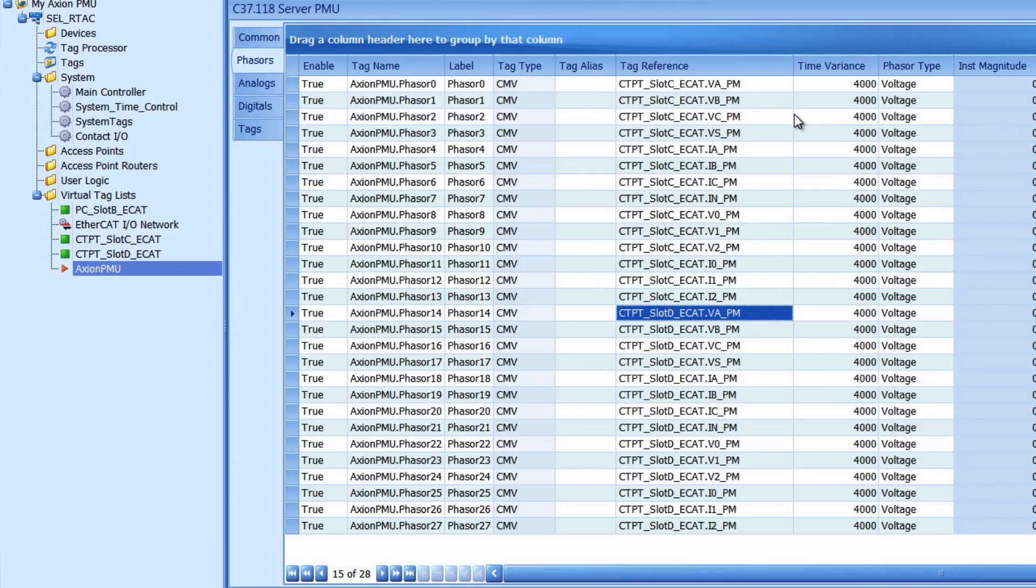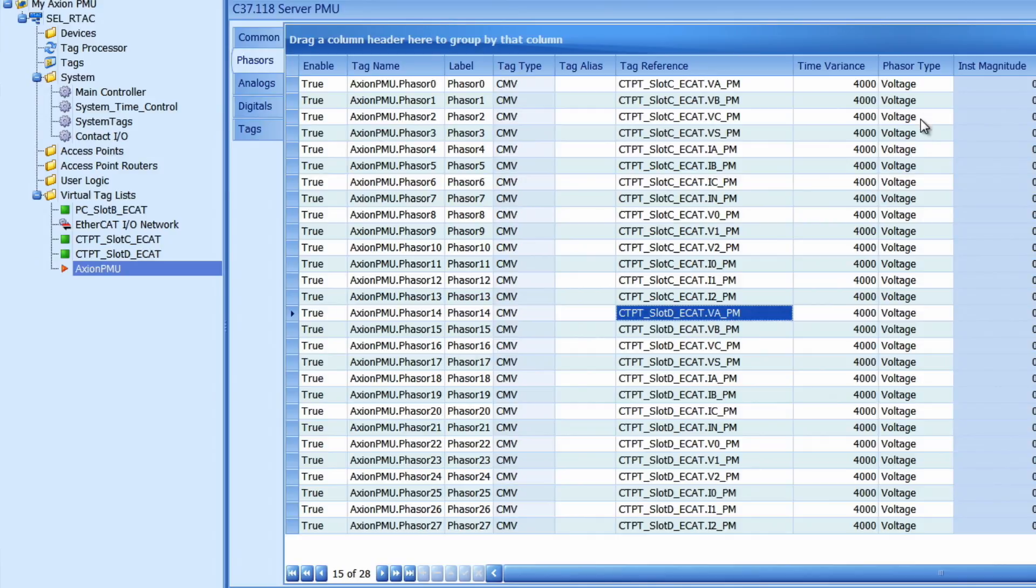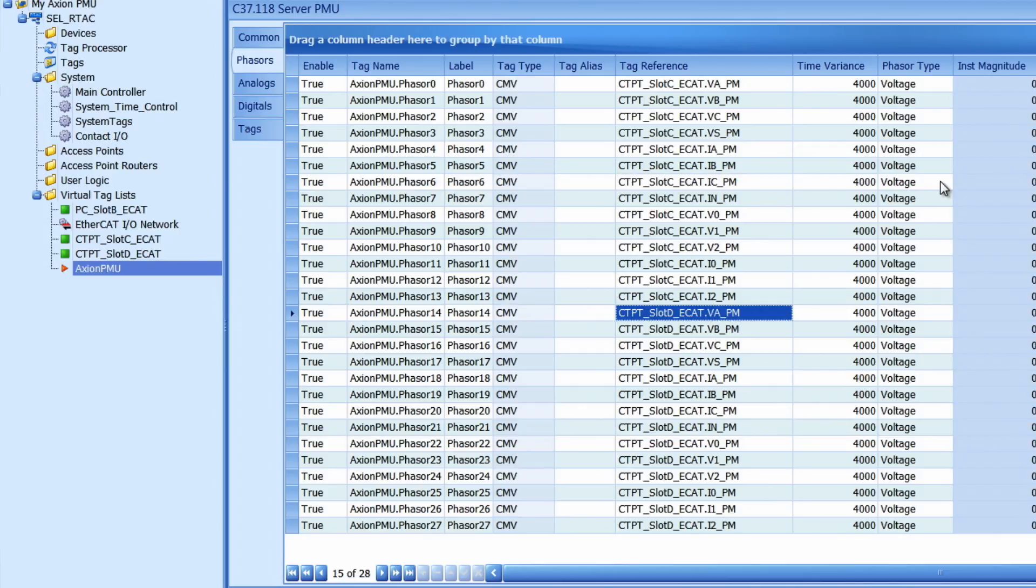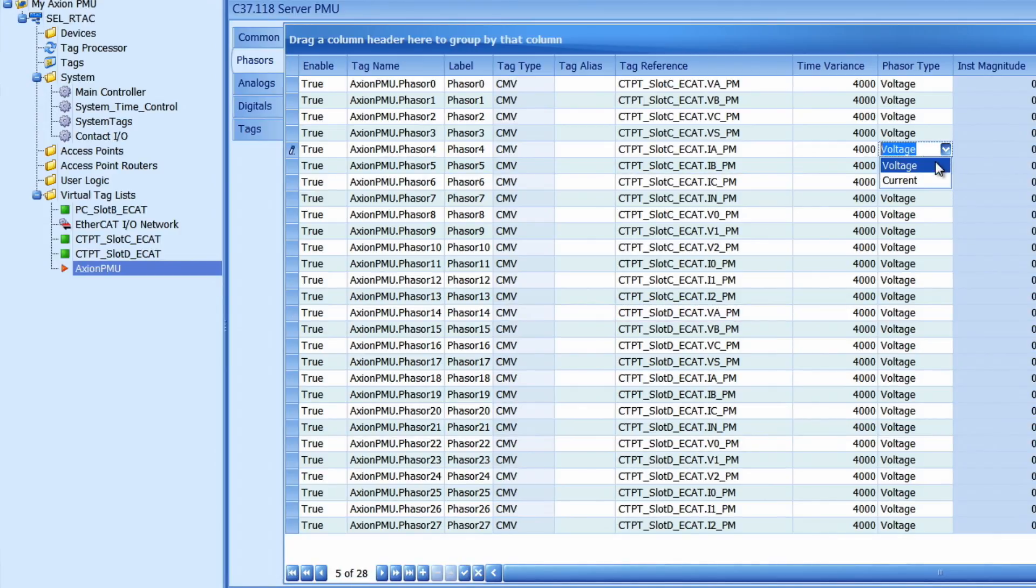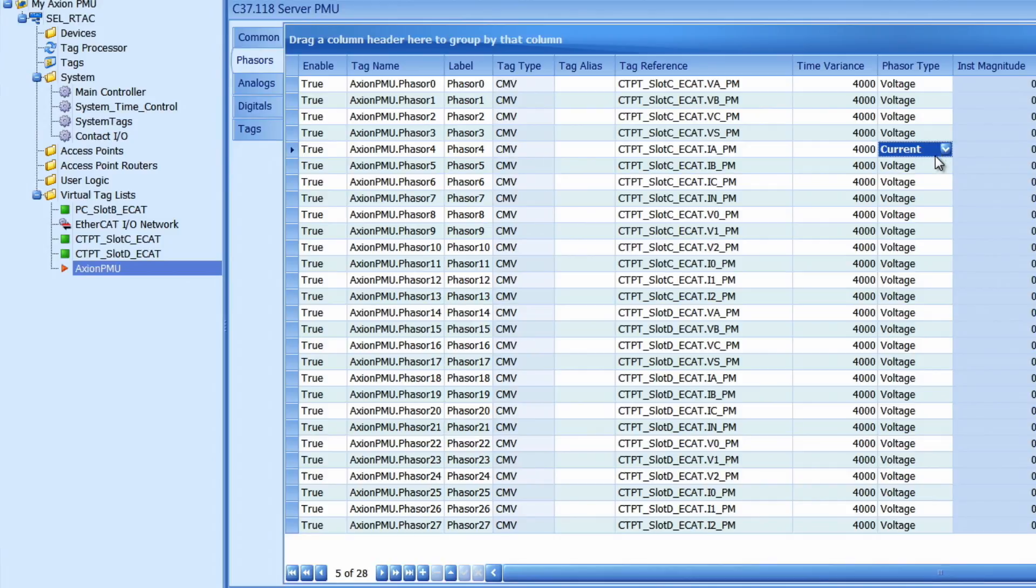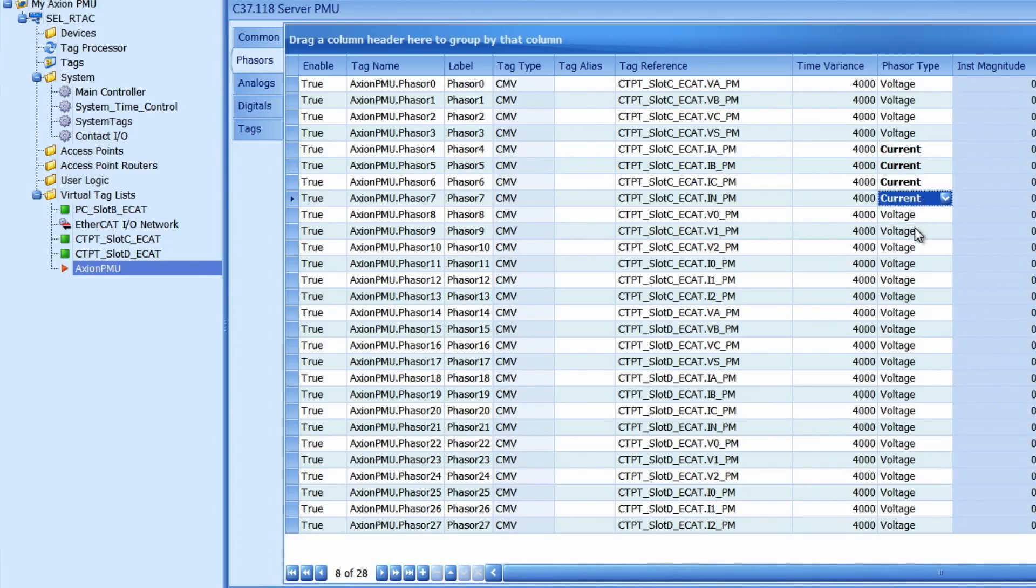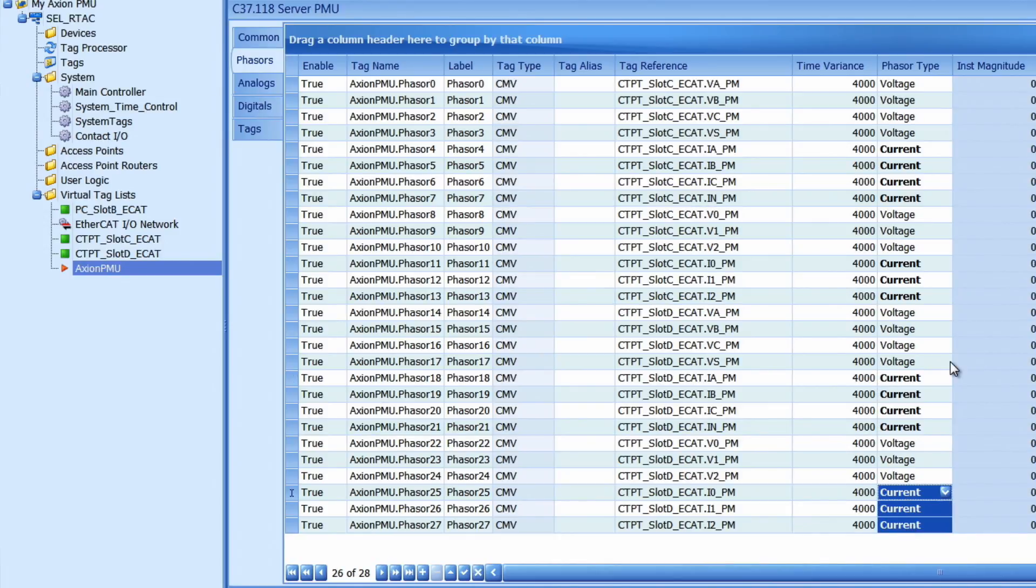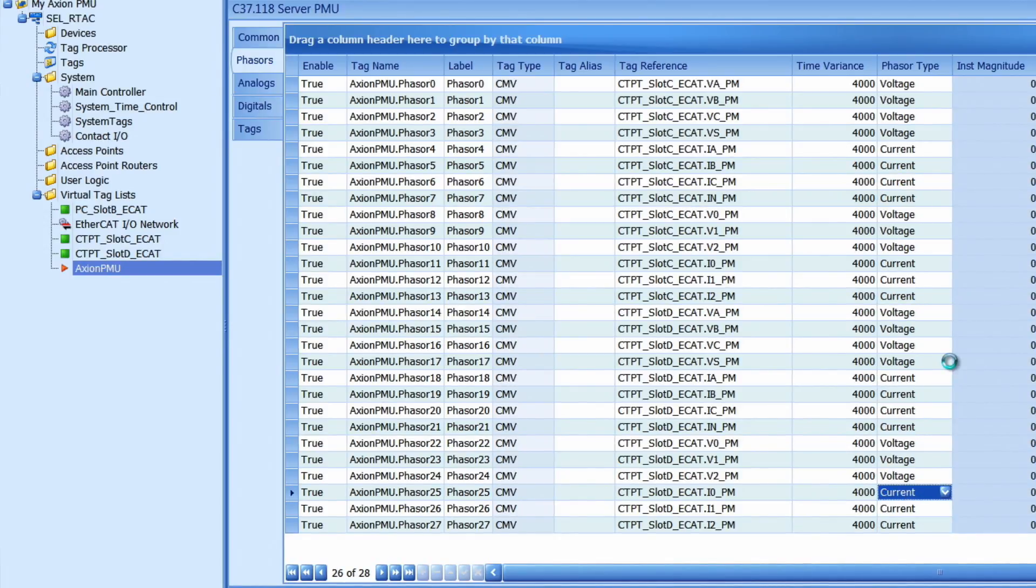One last thing I need to set here is the phasor type. By default all phasor types are set to voltage but I want to make sure that my phasor types are set correctly for the currents. All names with an I in it are representative of phasor currents. So I'm going to change each of those to a current. I can do that easily by using the copy and paste method. Once I have changed all the correct phasor types to match with the currents I'm going to hit control S once again and save it like that.